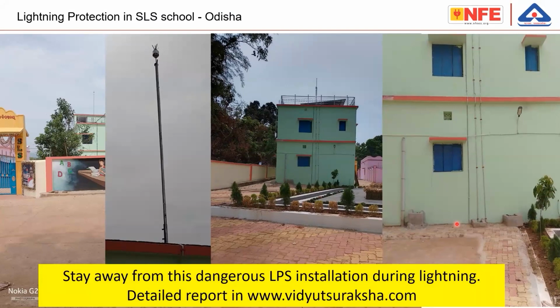Small children are going to play sometime in this area, and no one can control children and tell them you have to be inside the building. This is the boys' hostel in a school. Imagine during the afternoon, on a Sunday when no teachers are there, if children are playing outside near this down conductor, and there is a lightning strike, then they are in deep trouble. So such installations shall not be made. This is completely a violation of these standards.